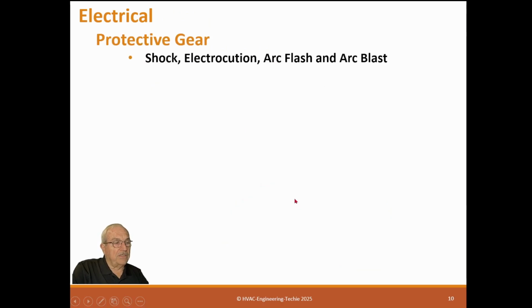Protective gear. This is important. Shock, electrocution, arc flash, and arc blast. Now, I know as test and balance guys, we always complain because we don't wear the stuff we're supposed to normally. I mean, normally we're cutting into a 208 box. We're not dressed up for 208. We're dressed up for 120, which is main standard stuff. No PPE, except for maybe safety glasses and gloves. Other than that, we won't be decked out. But that's a problem because we enter them all day long.